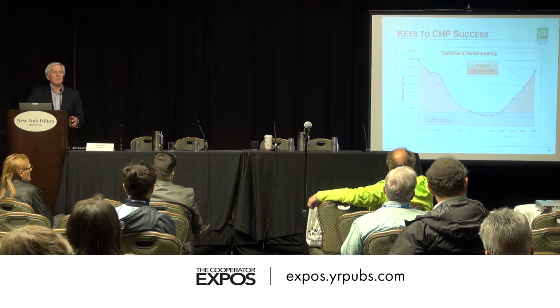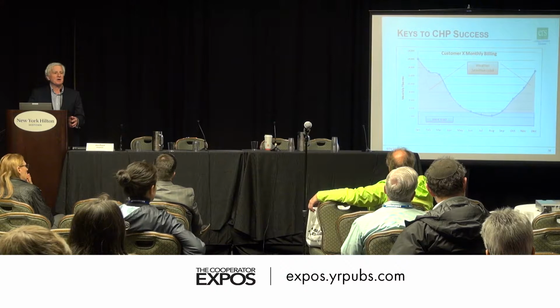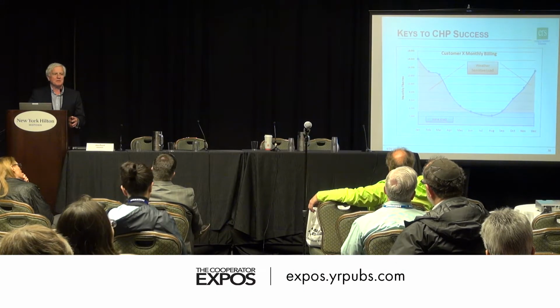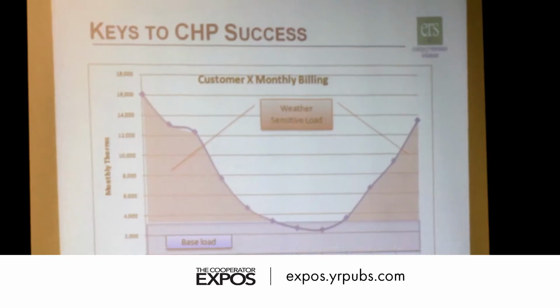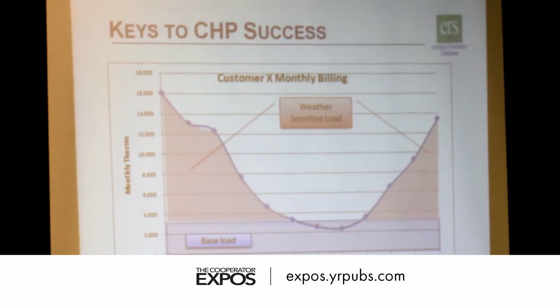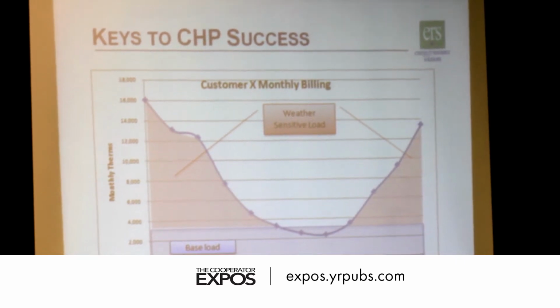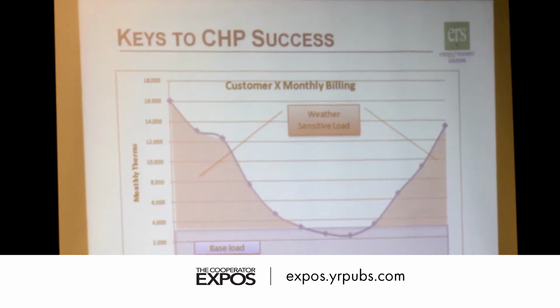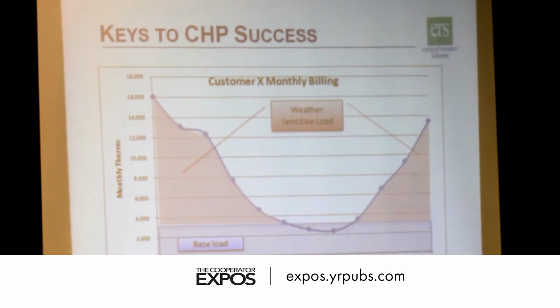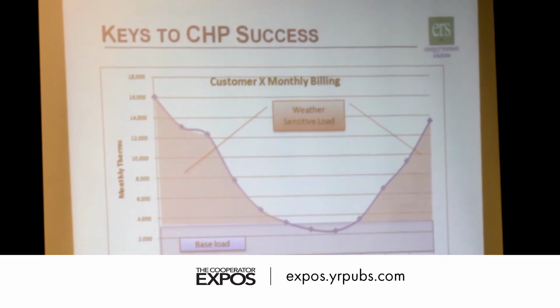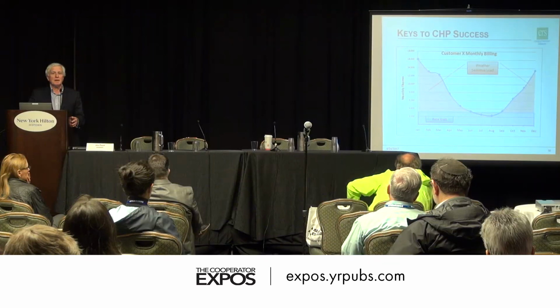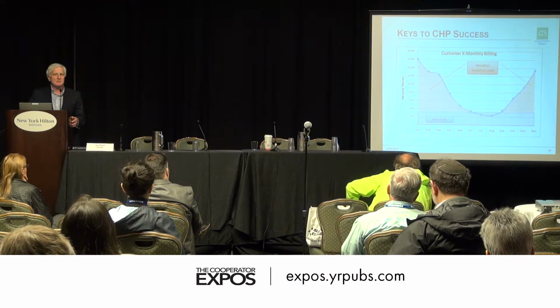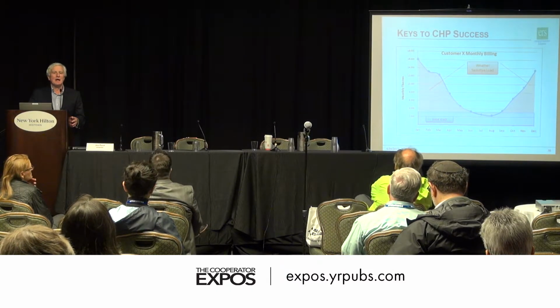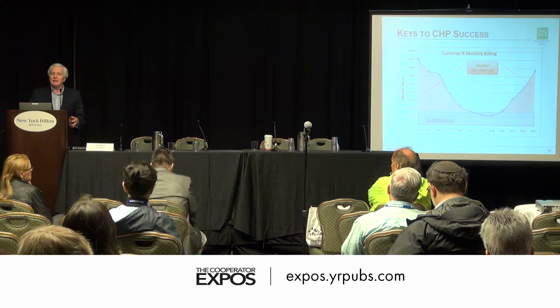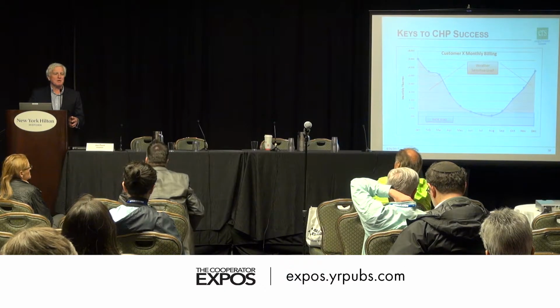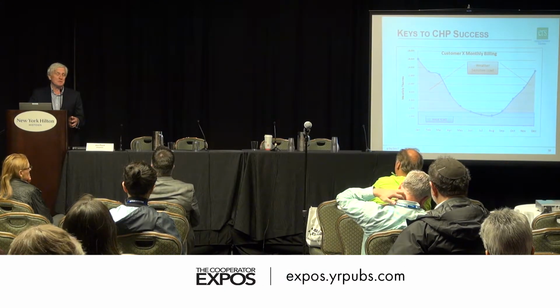I mentioned before the desire to match the size of a CHP system to a year-round load. This is a diagram of the heat usage of a building, with the blue part at the bottom being the base load, representing domestic hot water, and the upper part representing the heating load. It is possible to address a good part of the heating load, but for certain parts of the year that heat may not be usable. So it's best to think of addressing the base load, the domestic hot water load, and then do what you can to address heating loads on top of that.